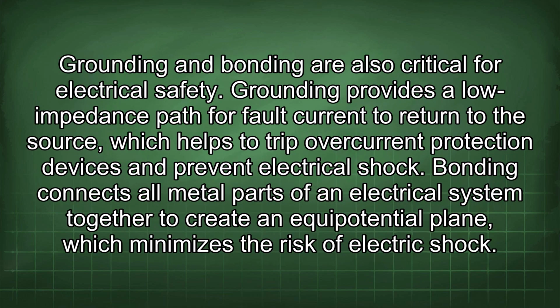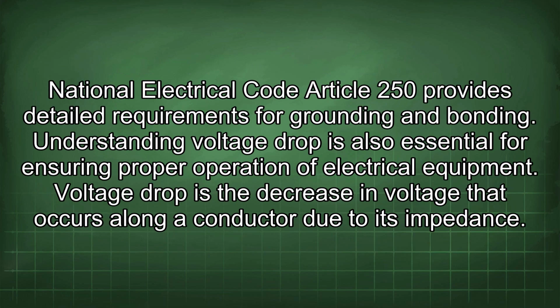Grounding and bonding are also critical for electrical safety. Grounding provides a low impedance path for fault current to return to the source, which helps to trip overcurrent protection devices and prevent electrical shock. Bonding connects all metal parts of an electrical system together to create an equipotential plane, which minimizes the risk of electric shock. National Electrical Code Article 250 provides detailed requirements for grounding and bonding.